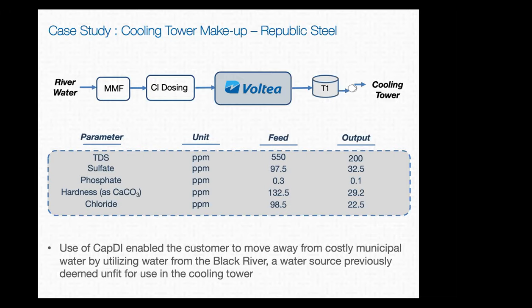So they would bring that water in, run it through the CAPDI system, run it through a treatment system. We would use a multimedia filter to remove any particulates again, chlorine dosing to remove any bacteria, run it through the Voltea system to reduce down that TDS, reduce the sulfates, reduce the hardness before sending it into the cooling tower. That way, because the water is much higher quality, they can cycle that water up in the cooling tower, use it for their process before sending it down to waste at the end of the day.